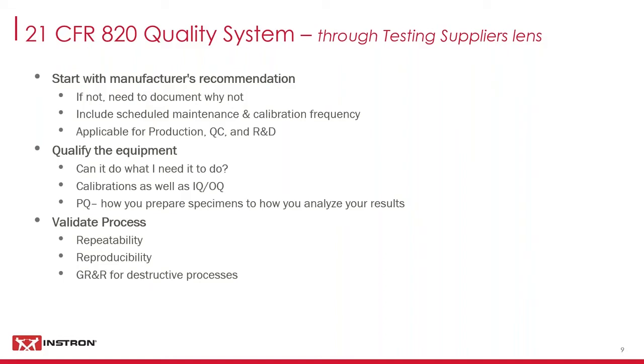We know our equipment, we know our software, and certainly we understand this process pretty intimately. Suppliers like us at Instron can help you enhance the quality of the process and additionally save significant amounts of time. The best approach, I think, starts with understanding the testing system manufacturer's recommendations. And we typically lay these out before we install systems or upgrades to software. Typically, if you're not planning to follow those recommendations, you should document why not. The recommendations include scheduled maintenance plans as well as calibration plans, including the frequencies at which you're going to be doing these things. And they're applicable across the board for production areas, QC areas, and R&D areas.